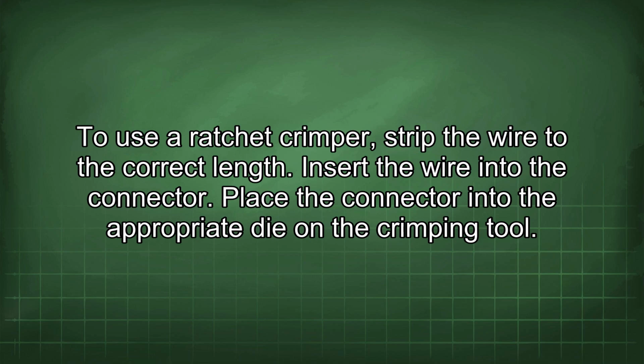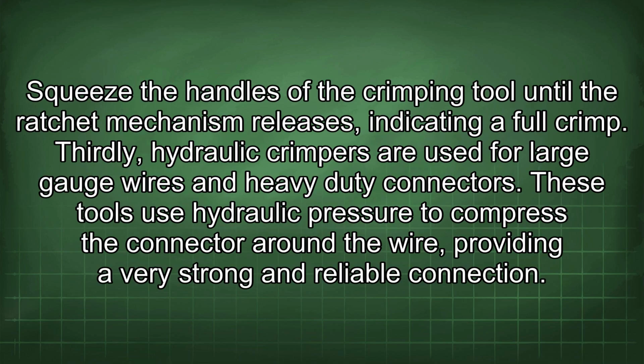To use a ratchet crimper, strip the wire to the correct length. Insert the wire into the connector. Place the connector into the appropriate die on the crimping tool. Squeeze the handles of the crimping tool until the ratchet mechanism releases, indicating a full crimp.